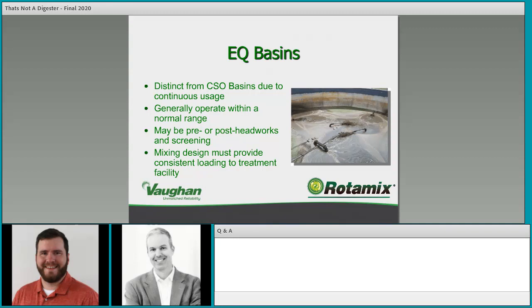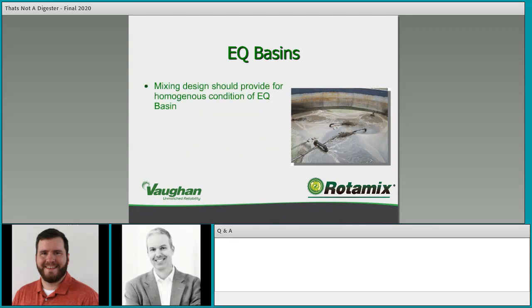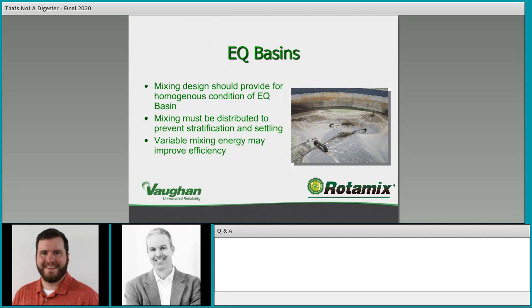The whole point of an EQ basin is to average things. Mixing design should provide a continuous mix that continuously homogenizes, blends, resuspends. You're in between the two factors of homogenization and agitation and resuspension — both are critical aspects of the design. Mixing should be distributed to prevent stratification and settling. Variable mixing energy may improve efficiency — you can vary mixing energy based on tank level, potentially seeing quite a bit of savings when running at lower levels.